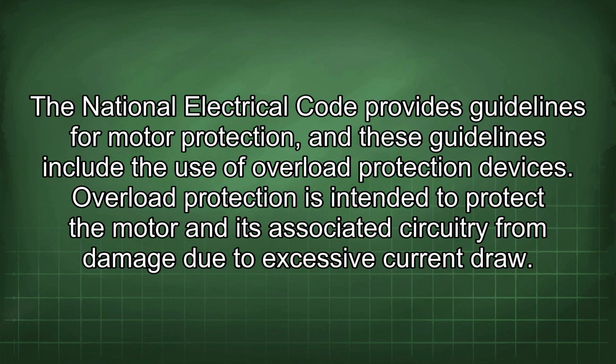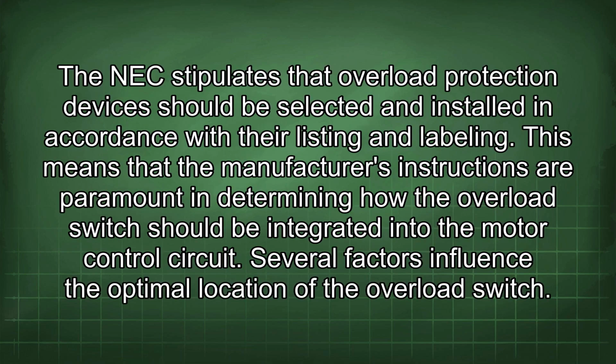The National Electrical Code provides guidelines for motor protection, and these guidelines include the use of overload protection devices. Overload protection is intended to protect the motor and its associated circuitry from damage due to excessive current draw. The NEC stipulates that overload protection devices should be selected and installed in accordance with their listing and labeling. This means that the manufacturer's instructions are paramount in determining how the overload switch should be integrated into the motor control circuit. Several factors influence the optimal location of the overload switch.